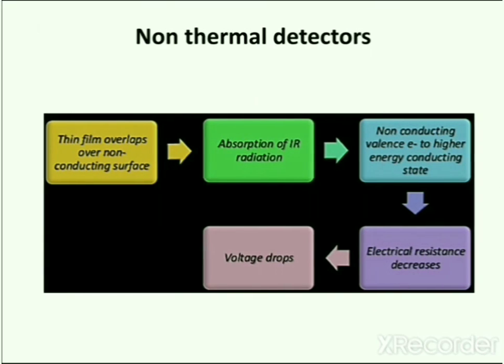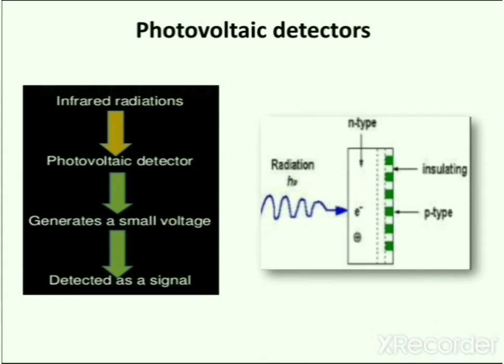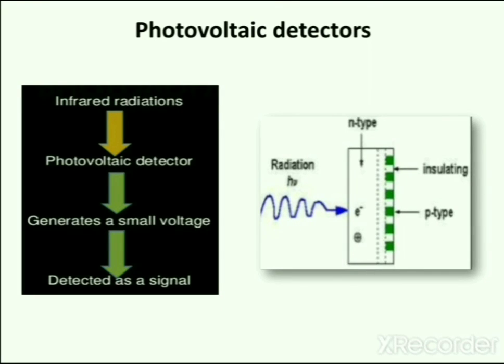The second type of detectors used in infrared spectrophotometers are non-thermal detectors. The response time and sensitivity of non-thermal or photonic detectors can be much higher, but usually these have to be cooled to cut thermal noise. The material in these detectors are semiconductors with narrow band gaps, and incident IR photons can cause electronic excitations. In photoconductive detectors the resistivity of the detector element is monitored, while photovoltaic detectors contain a p-n junction on which a photoelectric current appears upon illumination. When radiation from the sample is incident upon the photovoltaic detector, it generates a small voltage proportional to the incident electromagnetic radiation intensity. These devices are called photovoltaic cells due to their voltage-generating characteristics.